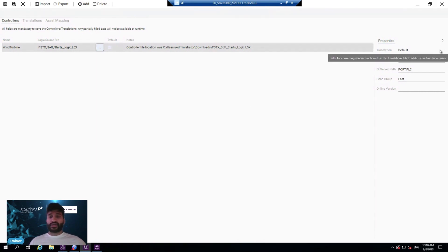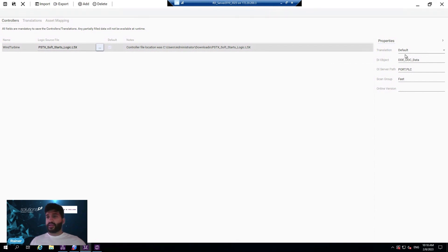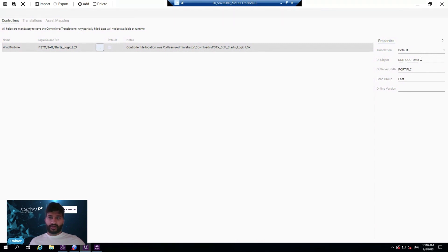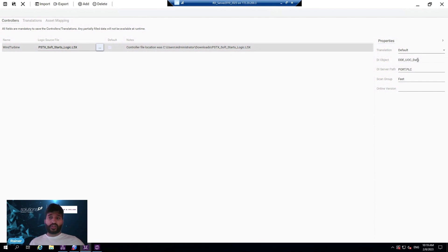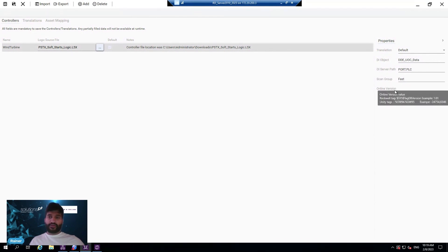We have translation information. If you're not able to see certain tags, you can translate them into tags that are familiar within the SCADA platform. You have the IO object, so you can link this information to real-time information from the PLC using our IO server. For those who don't know what an IO server is, it's your communication driver that talks to the PLC. This is the full path for the IO server - the scan group name - and you can also have the online version.